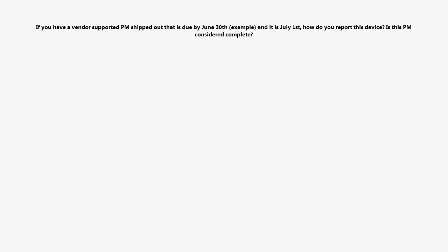So I can say PM with issue, sent out for calibration, sent out on the 15th of the month, didn't come back until the 10th of the next month, and my corrective maintenance work order will follow up. When it came back in, you did electrical safety on it, verified the operation had just been PM'd, and put it back into service.